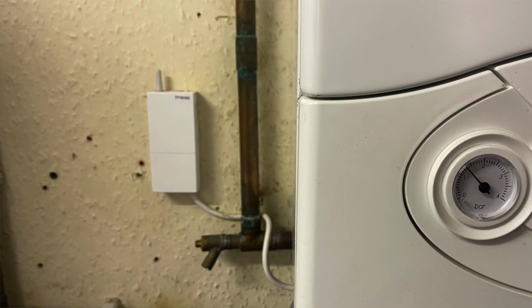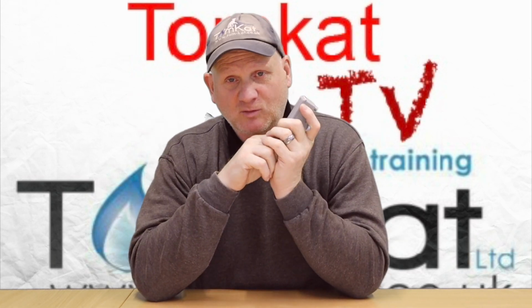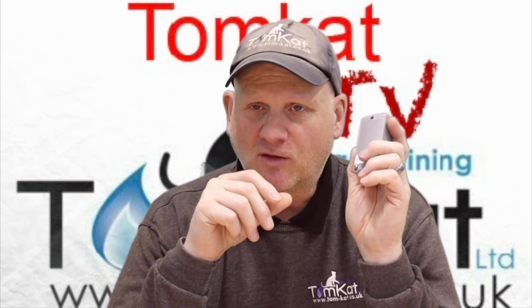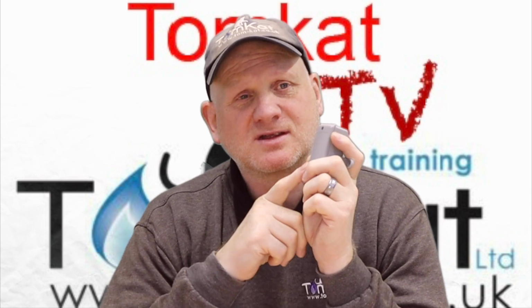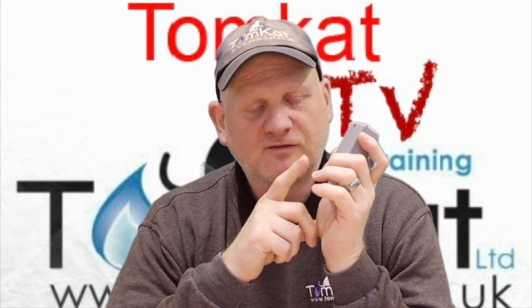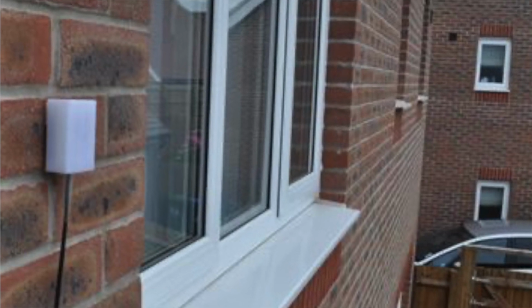So at the boiler there is a sender receiver unit, and this goes on a north facing wall. Now technically the north facing wall is best practice. You can actually put these on any wall as long as it's in a shaded area. So you could put them under the eaves, or you could put them behind downpipes or soil pipes, or you can even buy a cover for them. As long as they're not in direct sunlight, they will work, but a north facing wall in shade is the best place for them.